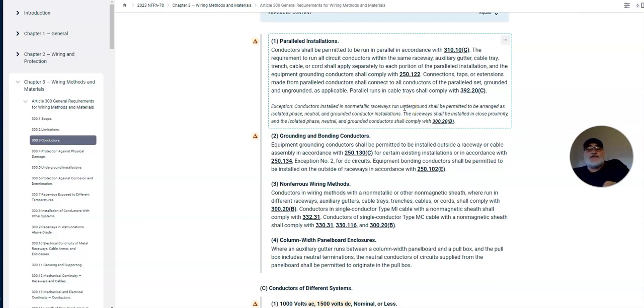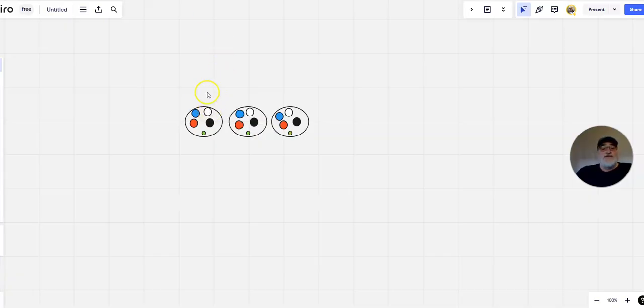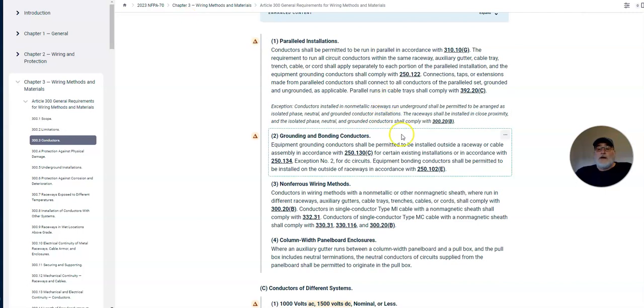So connections, taps, or extensions made from parallel conductors shall be connected to all conductors of the paralleled set. Again, what we're looking at is one paralleled set of three parallel. Grounded and ungrounded, the parallel set grounded and ungrounded conductors as applicable. Parallel runs in cable trays shall comply with 392.20(C). So let's look at the exception on this. Conductors installed in nonmetallic raceways run underground shall be permitted to be arranged as isolated phase, neutral, and grounded conductor installations. The raceways shall be installed in close proximity, and the isolated phase, neutral, and ground conductors shall comply with 300.20(B).